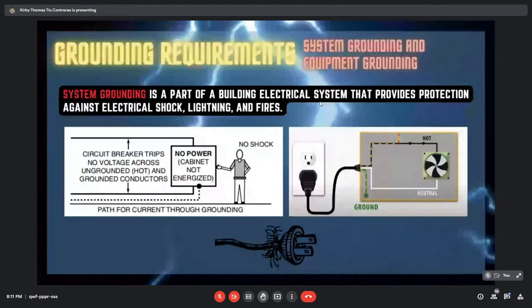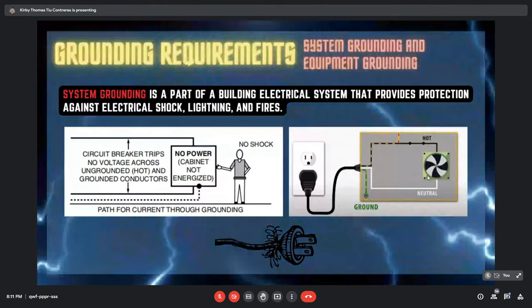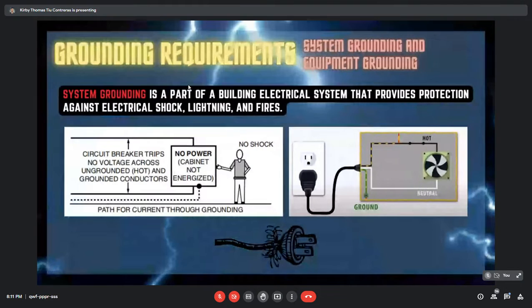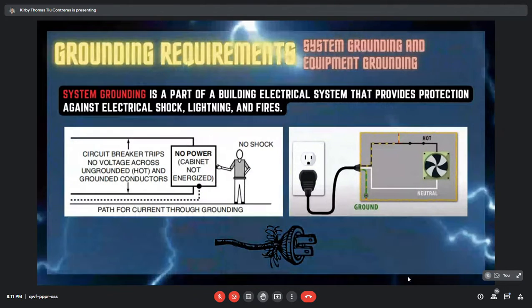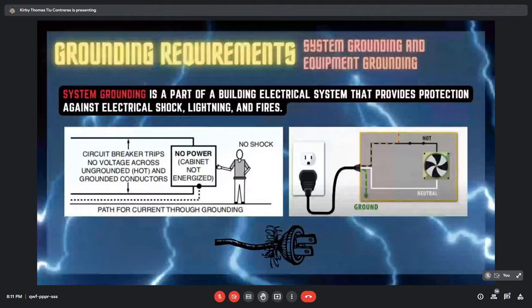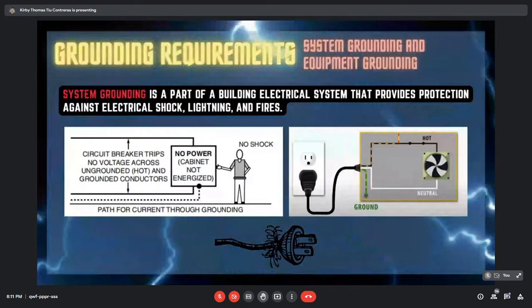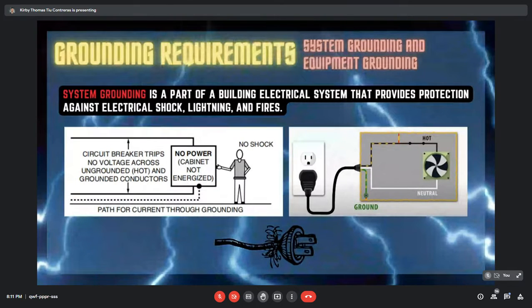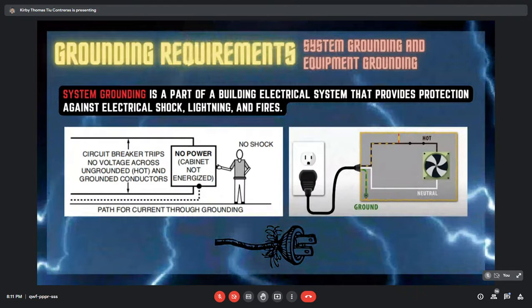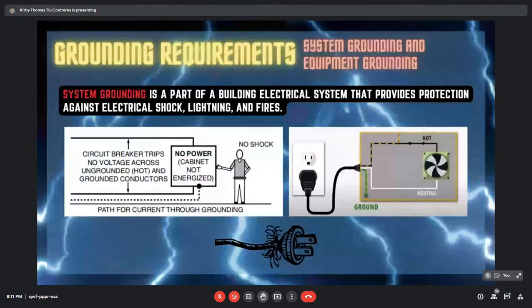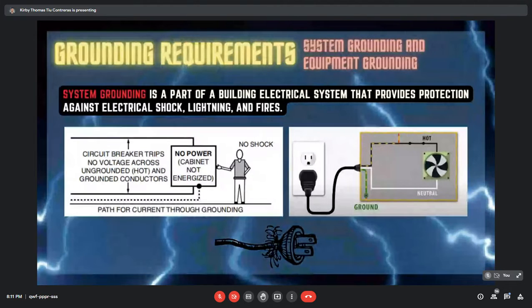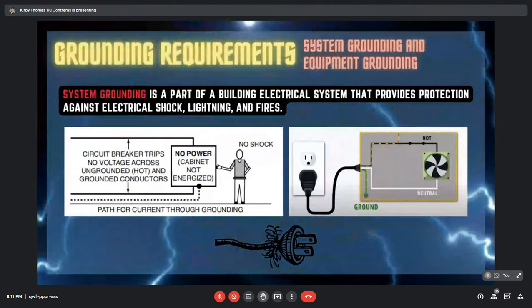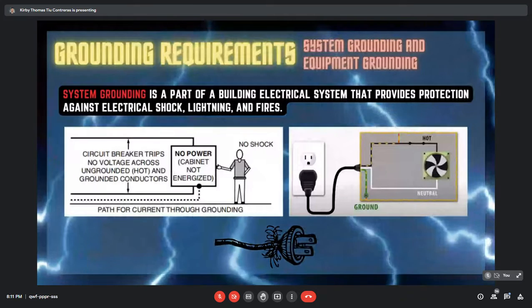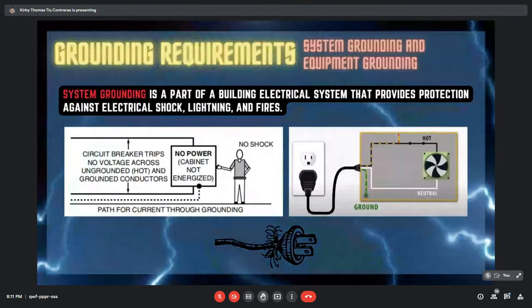System grounding is a part of a building system that provides protection against electrical shock, lightning, and fires. So, the figure below on the right side shows that since there is a ground, grounding of an electrical branch circuit enables current to take a path back to the overcurrent protection devices. That's why in cases where a device or appliance short circuits, the circuit automatically shuts down.